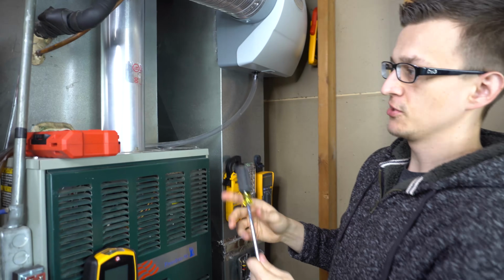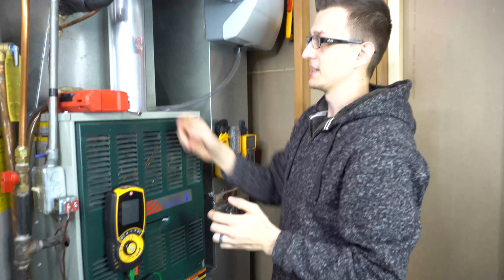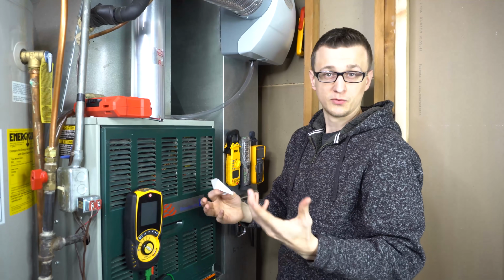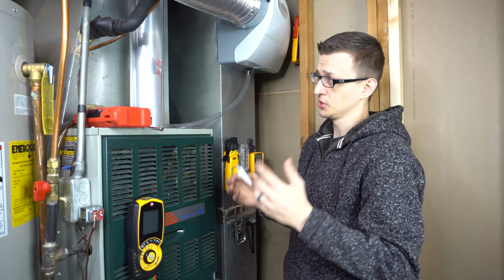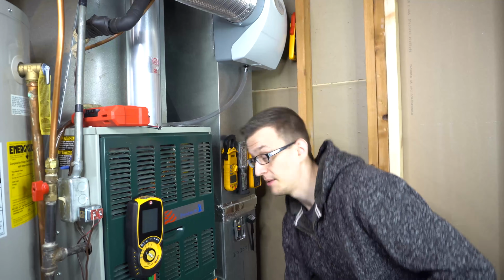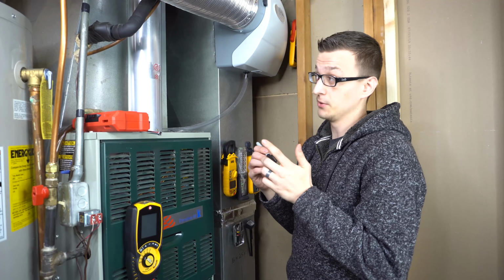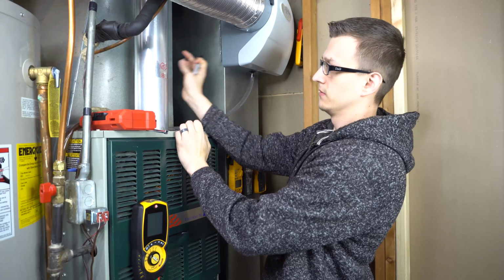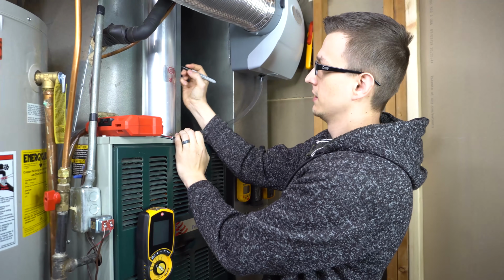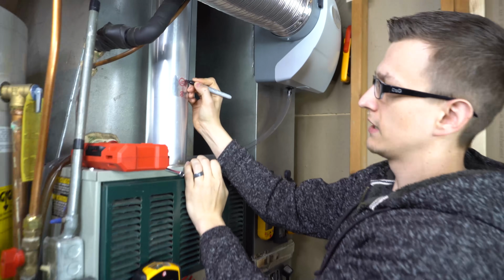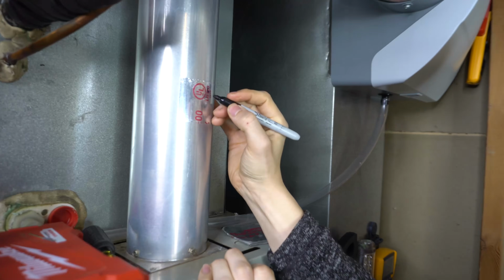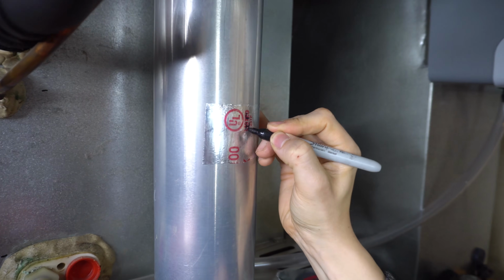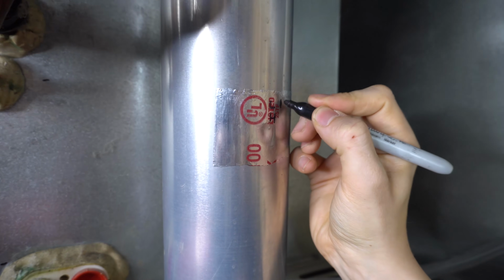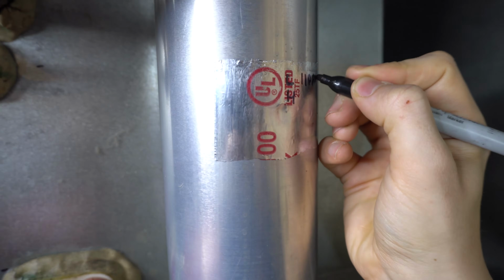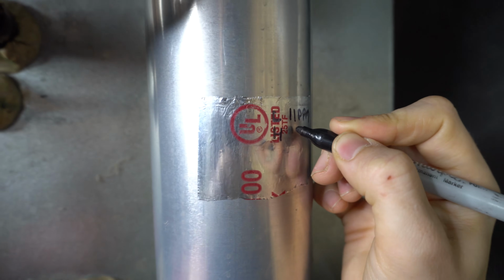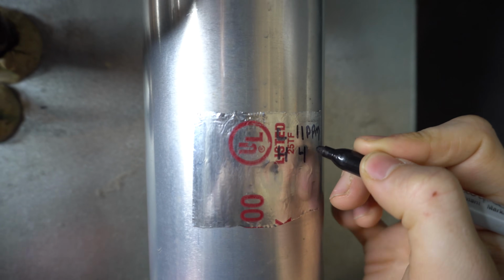Because this analyzer does not come with a printer, I mean, it's capable of communicating with an infrared printer, but it does not come with one, which is okay considering that it costs 2 or 3 times less than most of the analyzers out there. What I like to do is to just put L, that's going to be for my low stage, and then H for my high stage. Low stage was 11 parts per million. High stage was, I believe, 4 parts per million.